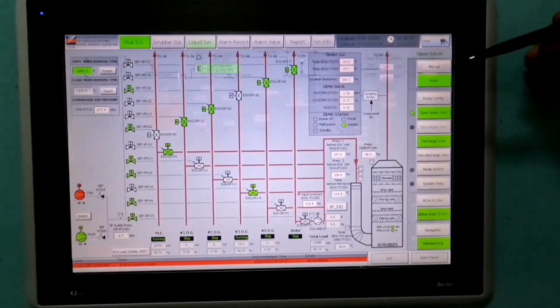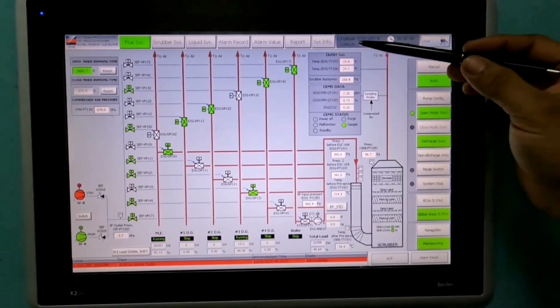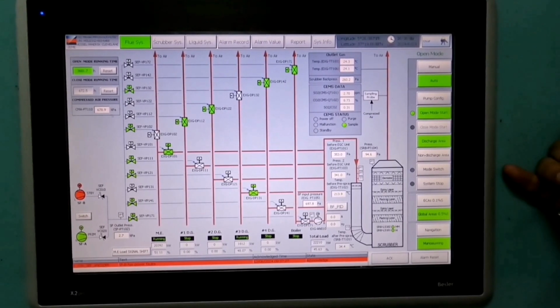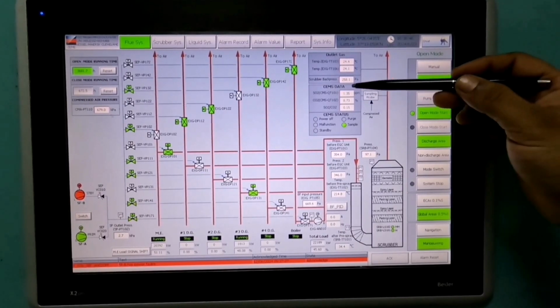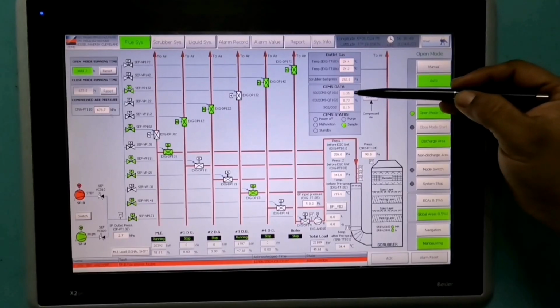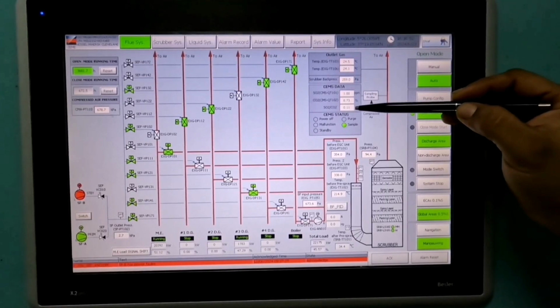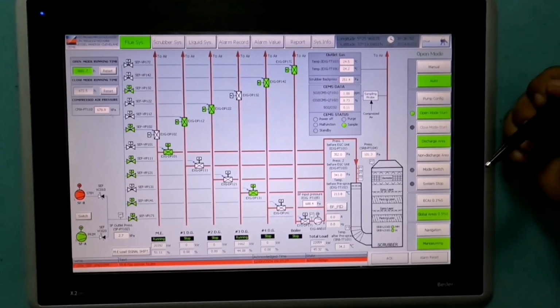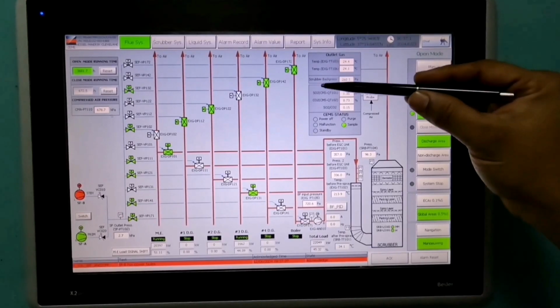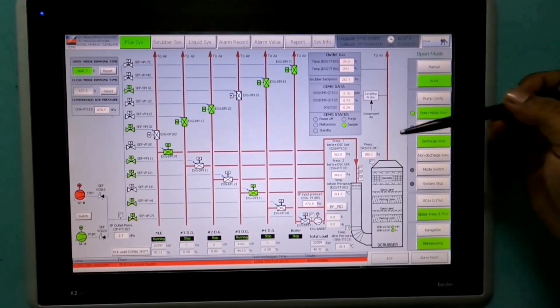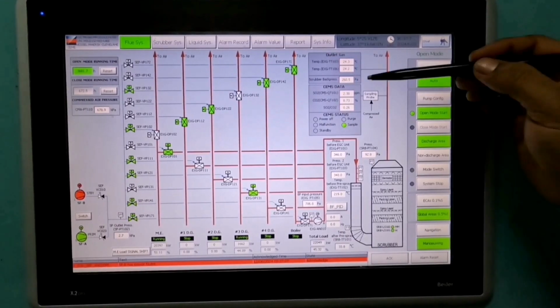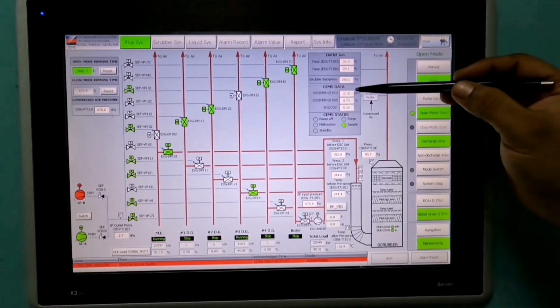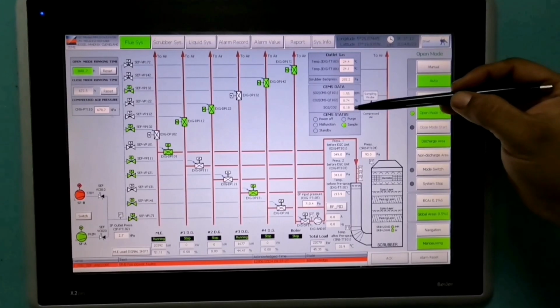And at the exhaust gas emission side, we have the CEMS unit. CEMS full form is Continuous Emission Monitoring System. This CEMS unit will show you the value of SO2 and CO2 and the ratio of SO2 by CO2. We have the limit: the SO2 by CO2 ratio should be a maximum of 4.3. So this is the basic idea, what is finally being monitored here is what we are emitting from the ship, meaning the exhaust gas content of SOx, SO2, CO2 and its ratio.